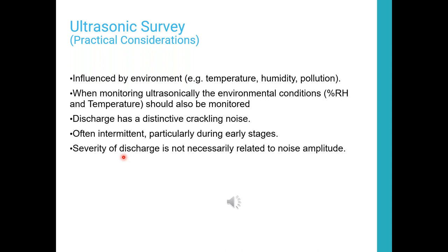One thing, your ultrasonic is going to be used, as I've said before, for surface discharge. Surface discharge is influenced by the environment. So humidity plays a big factor in the amount of surface discharge you'll see. I was at a facility where they had known partial discharge. We went in with the handheld instrument, tested it. We found a section that had it. We were going to put a full-time monitoring system in.